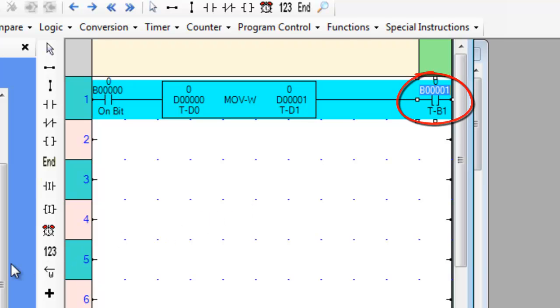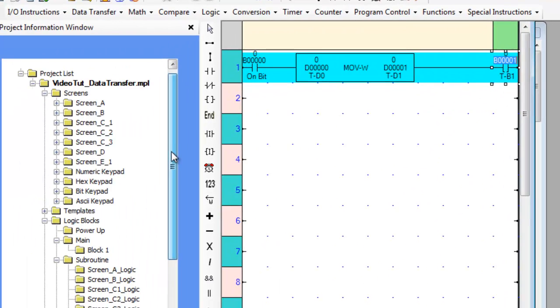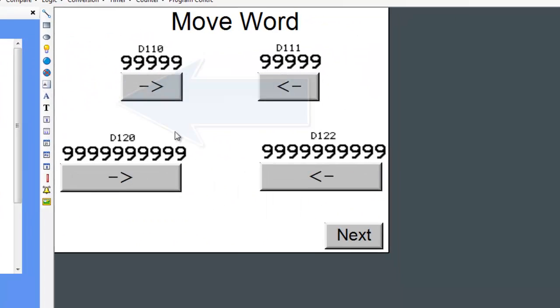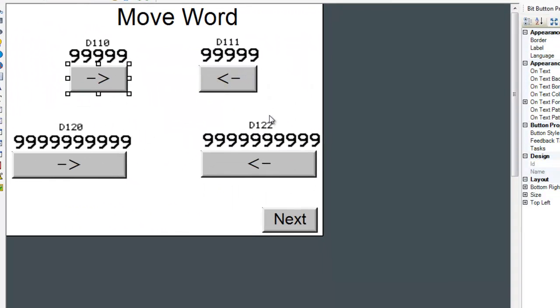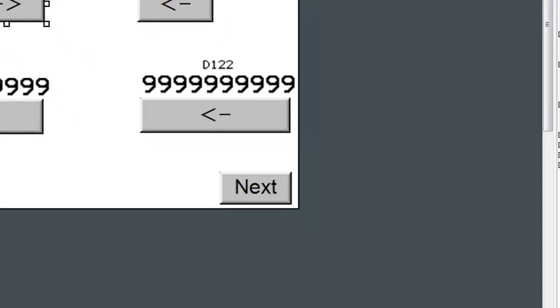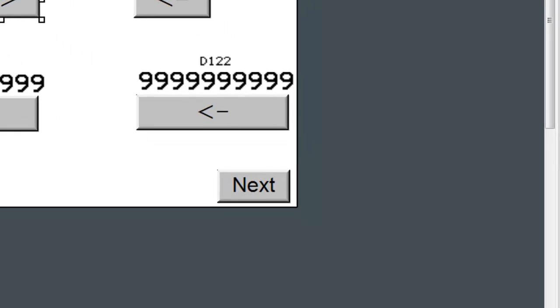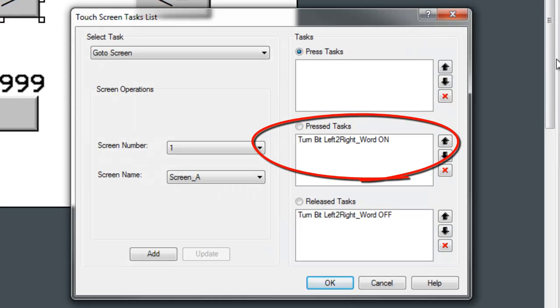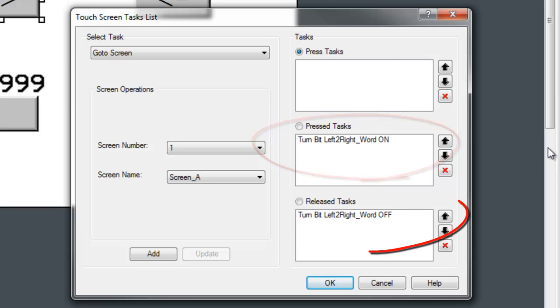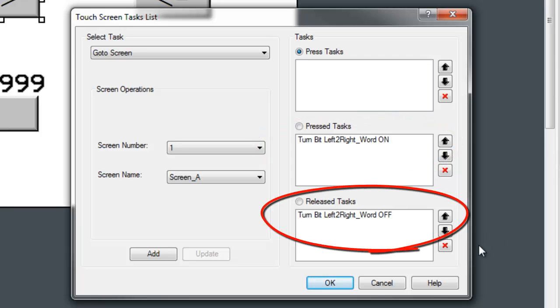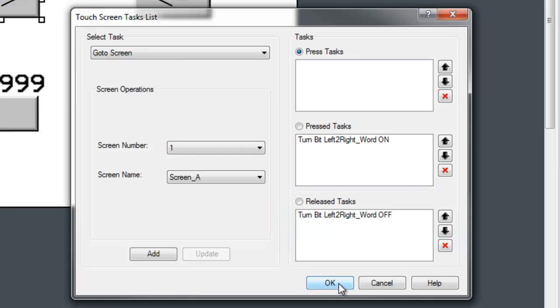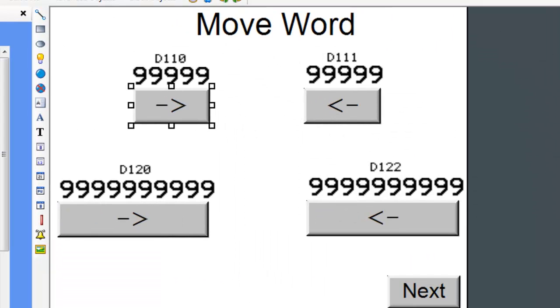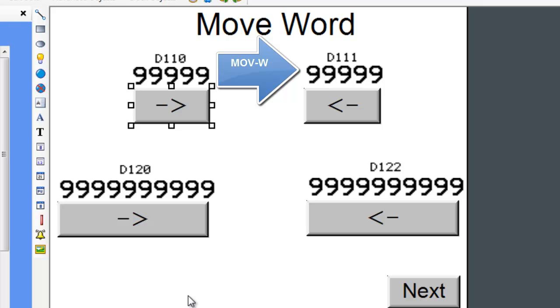Let's observe the slider instruction by scrolling to screen A. Similarly, when the button underneath the D110 data register is pressed, the corresponding coil is turned on. When it is released, the coil is turned off. When the coil is turned on, the move word ladder instruction will be executed. The block copies the source register D110 and moves it to the destination register D111.